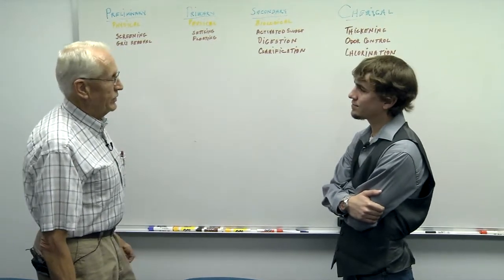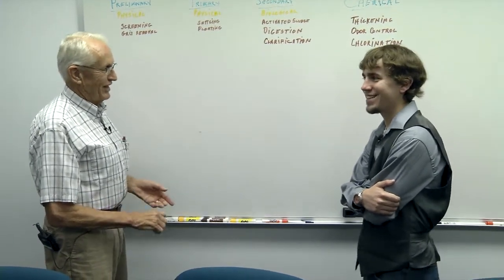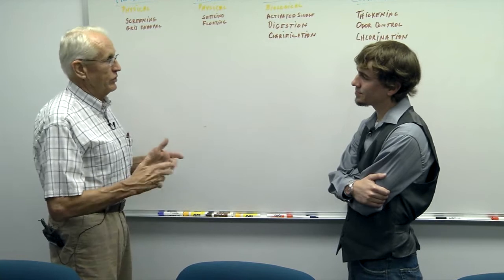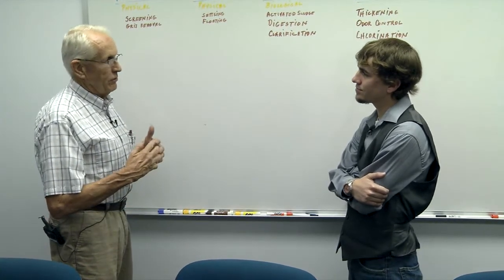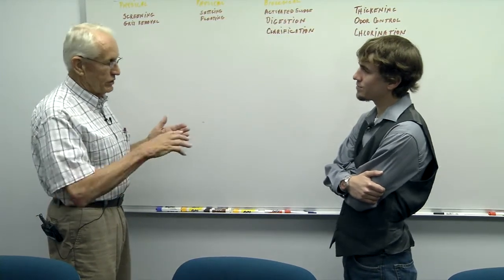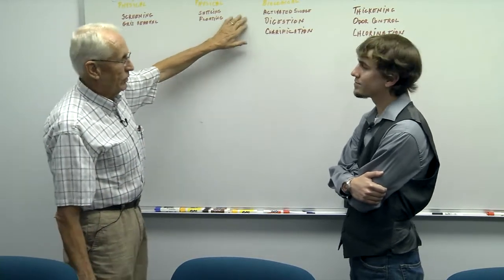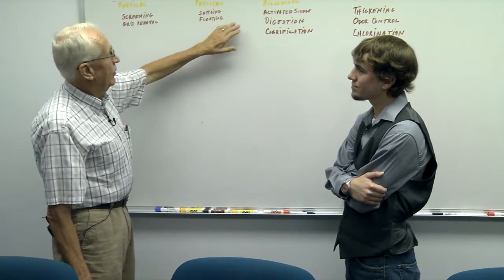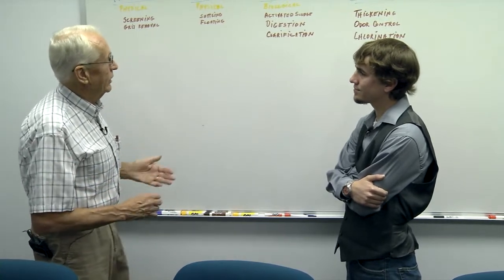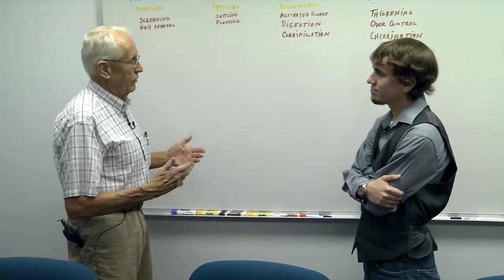The activated sludge system that we have is called an MLE, Modified Ludzack-Ettinger System. And that is? That came from South Africa, actually. Dr. Barnard was the man that came up with the treatment process. All it is that we have the first 3 stages are actually anoxic, which means there's no air, basically. We really just mix it very gently. In those stages is where we do our biological nitrogen removal and our uptake of phosphorus. Once it goes through those first 3 stages, then it goes through a regular activated sludge. All it means is that we're just treating it with air. We're doing the things that we would normally do to keep the bacteria and other organisms strong.